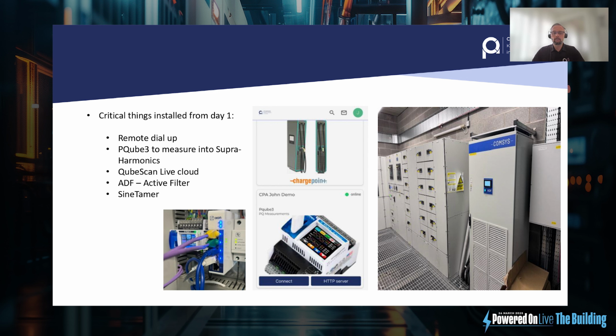We didn't install, sorry. We supplied a remote dial-up device, the PQube3, the harmonic filters and the supra-harmonic filters, so the ADF and the sine tamer, and we had that all in the cloud for the client. And on their first project, it was essential because they actually had some significant problems, both in design of the output of the EV chargers, which we fed back on how they were operating, what kind of noises they were creating, so that the manufacturer could actually modify the software to improve the situation. In addition to that, they did have a problem on a specific part of the job, and we identified what that problem was for them and resolved it with them.